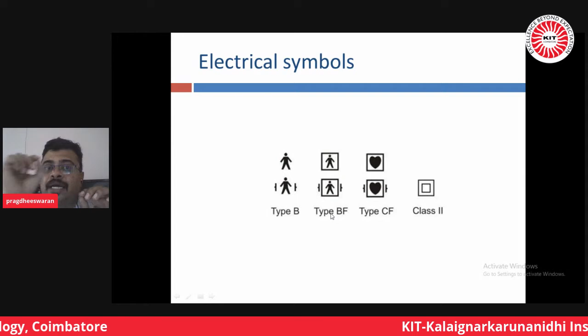Why? When you are doing that, you may be changing things. Say, for example, in a power supply, a capacitor failed. You are a biomedical engineer, or a manufacturer is coming and changing the capacitor. The capacitor on the equipment has, say, an effective series resistance of 1 milliohm as per the medical standards. Your service engineer comes, sees 1000 microfarad, 25 volts, goes to the market, buys the same 1000 microfarad, 25 volts, and replaces it. But this one has 10 milliohms of effective series resistance. Because of that, the ripple will increase. Because of the ripple increase, there will be a cycle of changes which will increase the leakage current of the equipment, which causes the leakage current to increase during the single fault. It's the same scenario. Some other single fault condition is also occurring. The mains power earth is drained off.